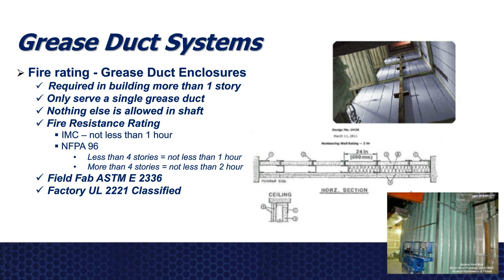Now, the shaft not only provides protection for that fire to spread from the kitchen to the rest of the building, but in essence, it's also a safety barrier if that ductwork has some kind of catastrophic failure with the fire inside of it, to keep it from spreading inside the rest of the building as well. So you really look at a shaft as two parts, I guess. One is keeping the fire from going from the kitchen, and two is if you had a catastrophic failure of the ductwork, if I'm in a fire-rated shaft, that's also going to serve as some level of protection because that fire-rated shaft would only have one grease duct and no other components inside of it.